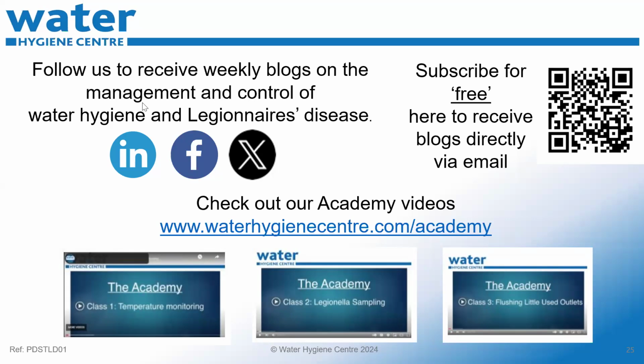Yes, you are. With children, we've probably got TMVs on there, thermostatic mixing valves. So those would need to be checked on a regular basis, 6 monthly for a fail-safe and annually for a strip down, depending on the manufacturer's details. You're looking at cold temperature checks, hot temperature checks, flow into the TMV and flow out of the TMV, make sure it's between the designated temperatures of 38 and 43, I think it is. And yeah, those things should be checked on a regular basis, but you are on the right path.